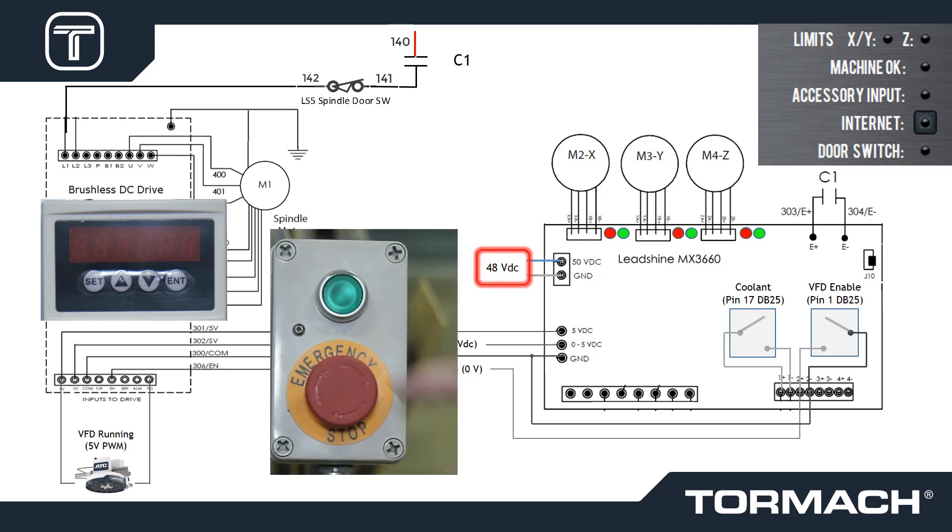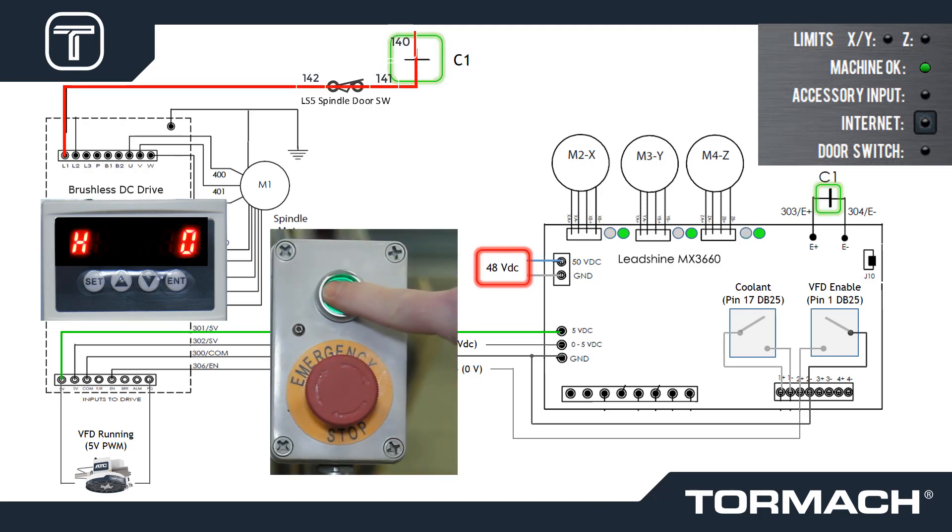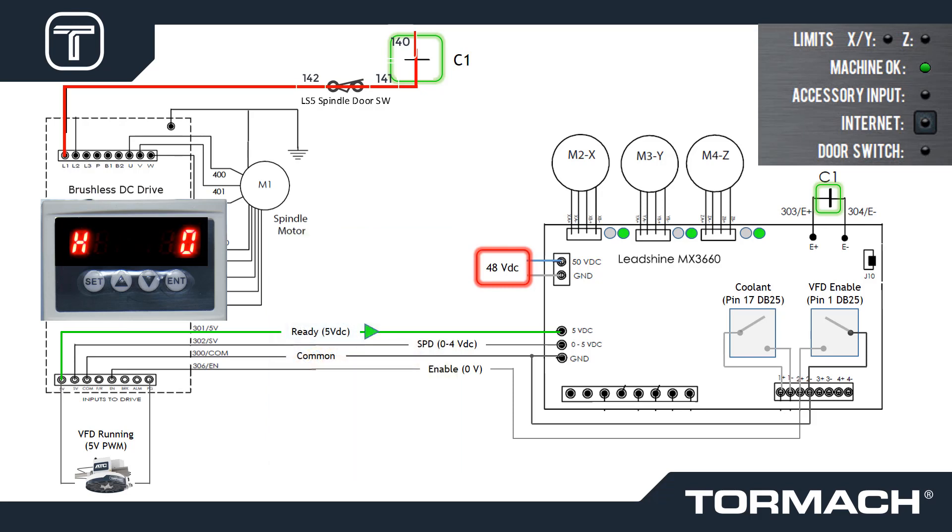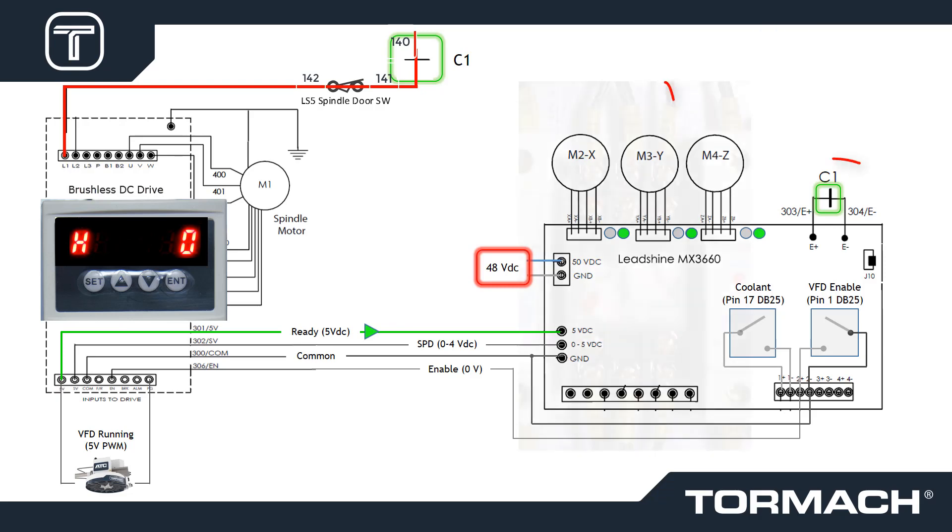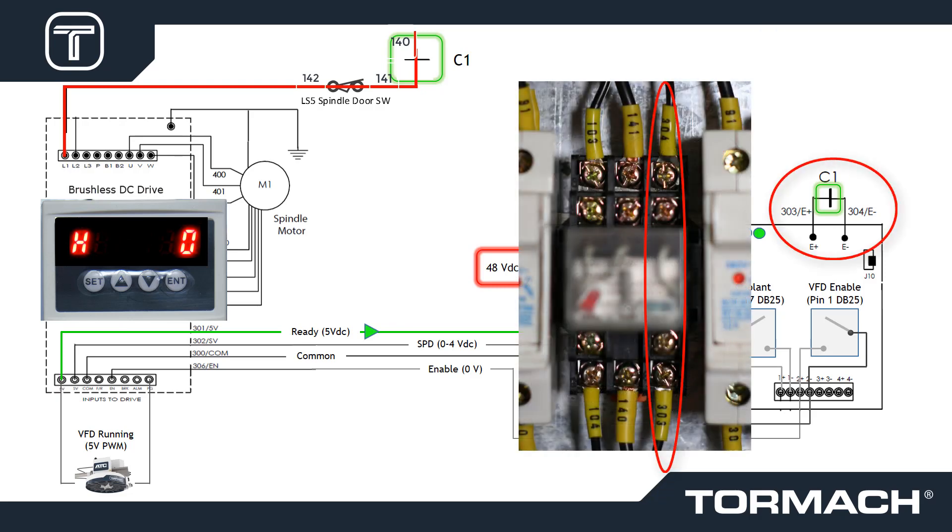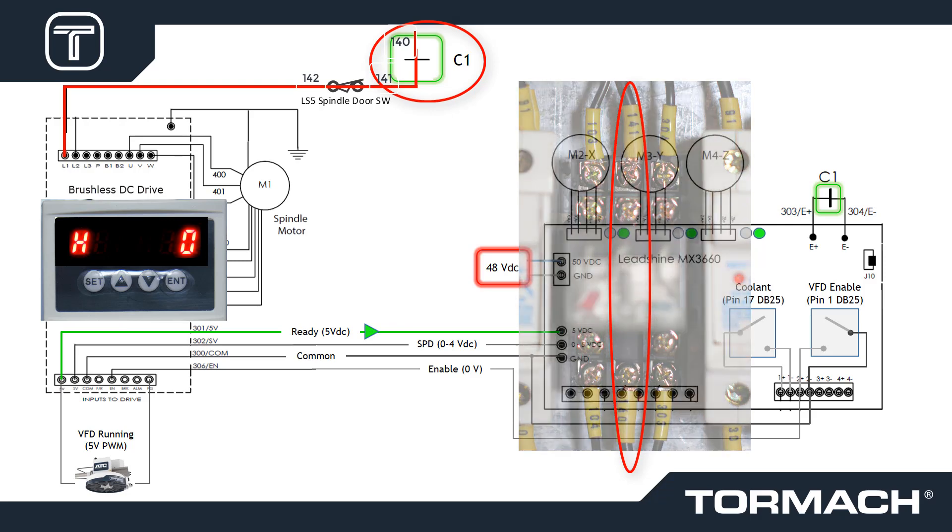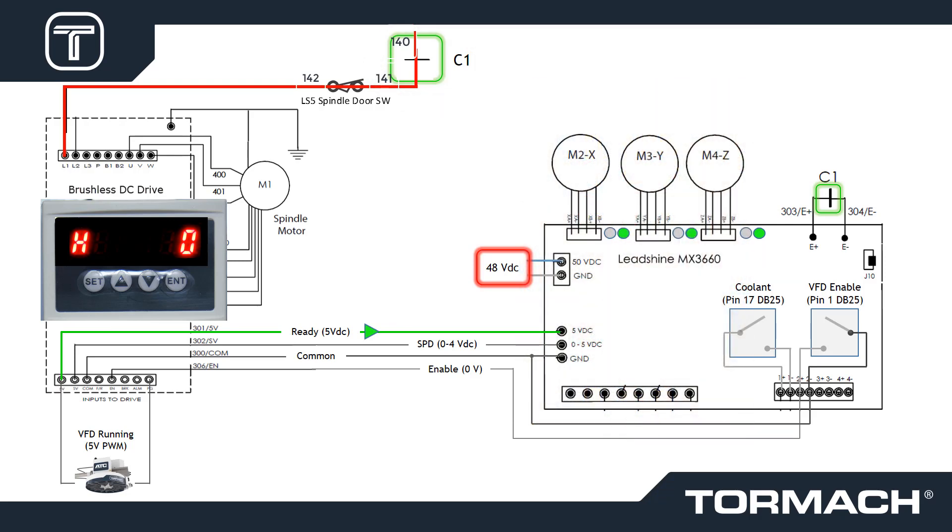Pressing the start button latches a C1 contactor. One of the four pairs of the C1 contacts enables the MX3660 via wires 303 and 304. Contactor C1 also powers the brushless DC drive, which we'll refer to as BLDC. When powered, the BLDC displays H0.